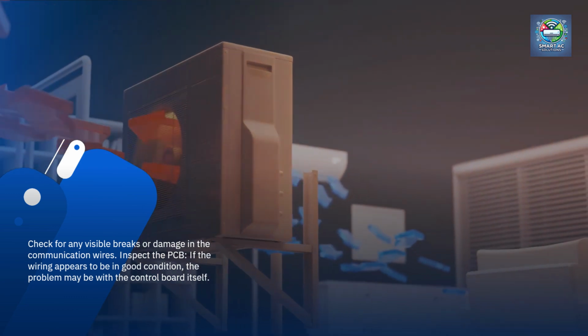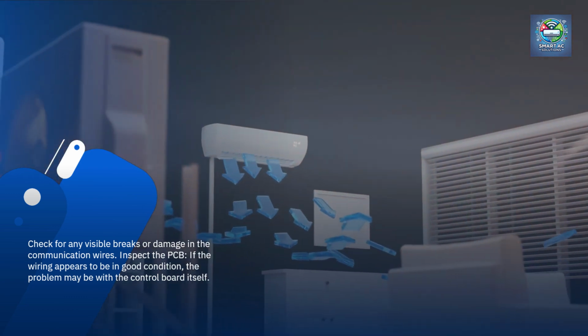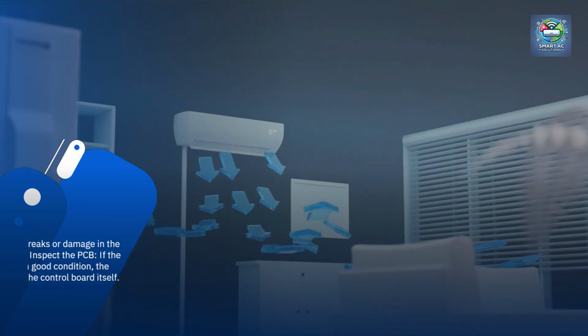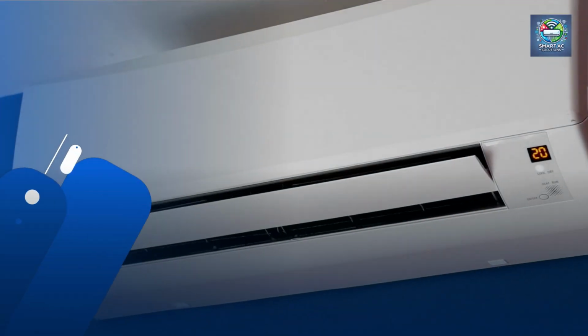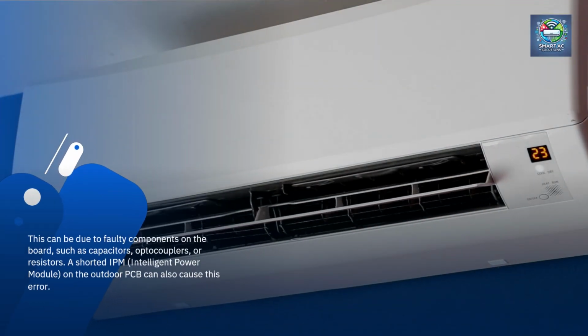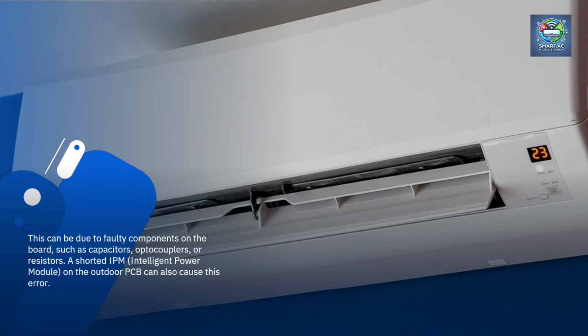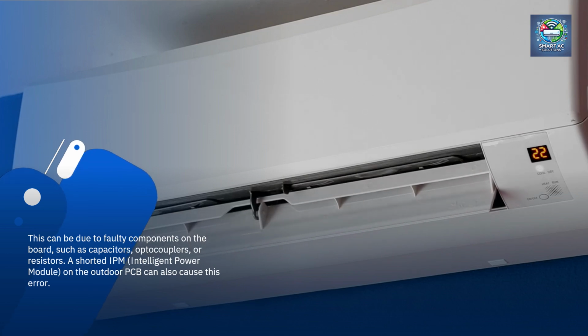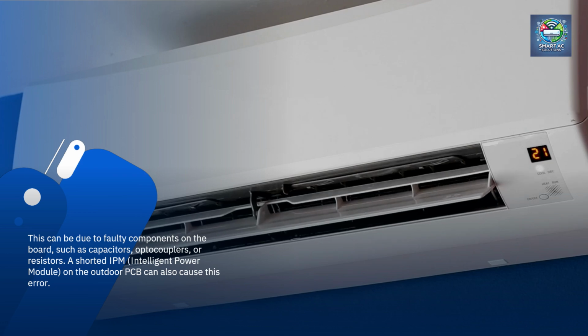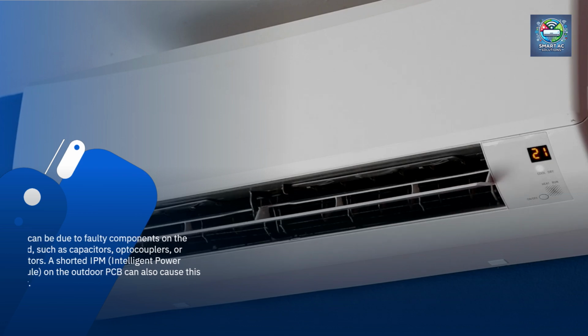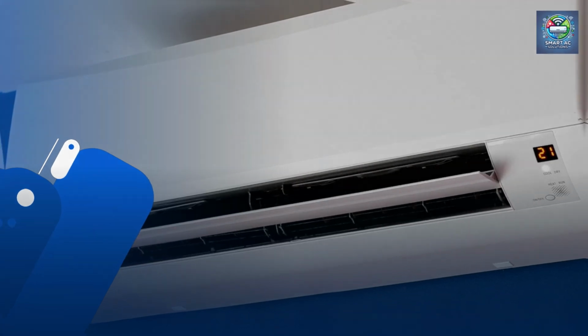Inspect the PCB. If the wiring appears to be in good condition, the problem may be with the control board itself. This can be due to faulty components on the board, such as capacitors, optocouplers, or resistors. A shorted IPM, intelligent power module, on the outdoor PCB can also cause this error.